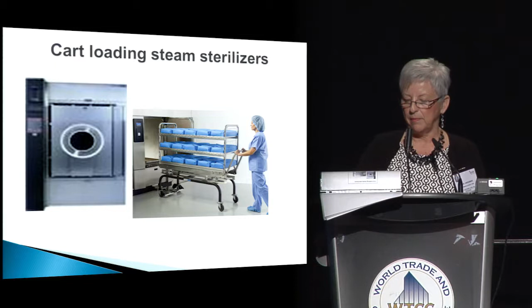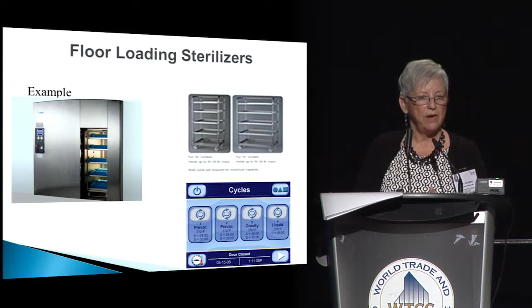The next one is a floor loading sterilizer, and this is a more modern sterilizer. The whole cart, including the wheels, will go into the sterilizer. There are older ones around, and they are really good workhorses. Some of these floor loading sterilizers actually come as a pass-through sterilizer, and the pass-through sterilizers, of course, keep that one-way workflow happening all the time. You package, sterilize, and it comes out into your case cart pick area. All sterilizers today have several cycles, and there are different ways to enter the parameters for your sterilization. This particular one can do some gravity, and it also can do some liquid cycles. There are many different cycles and lots to learn around these.